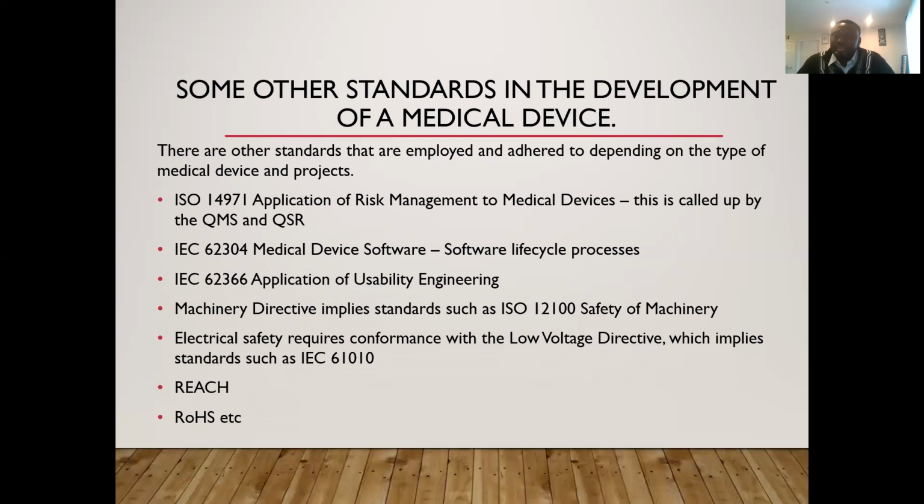So software which is defined as a medical device also has to adhere to this standard. There's the usability engineering application, which is IEC 62366. And then there's machinery-derived implied standards, such as ISO 12100 for safety of machinery. There's also the electrical safety requirement, which is IEC 61010. There's also REACH and RoHS compliance, which are also part of the standards that are needed.